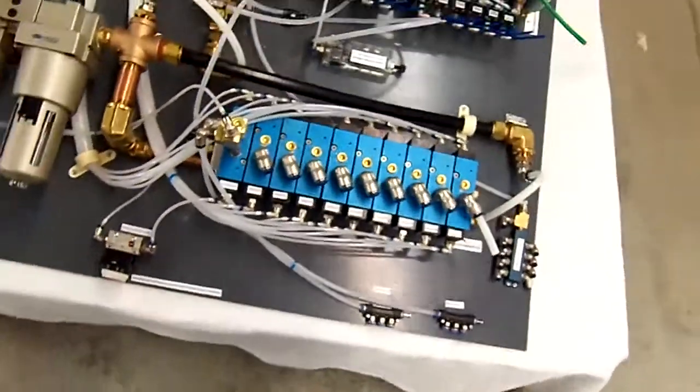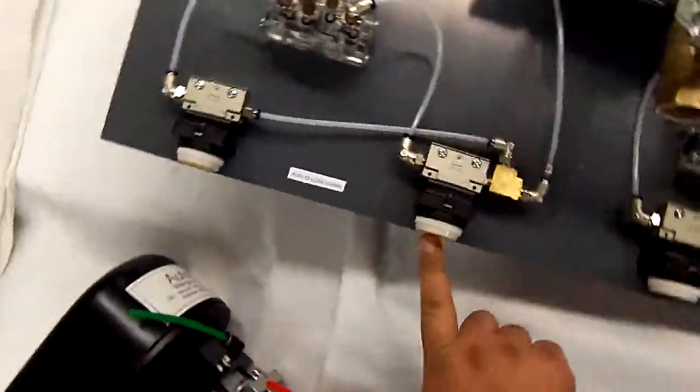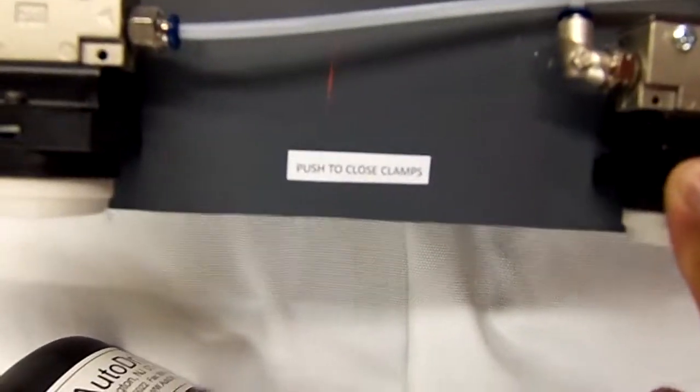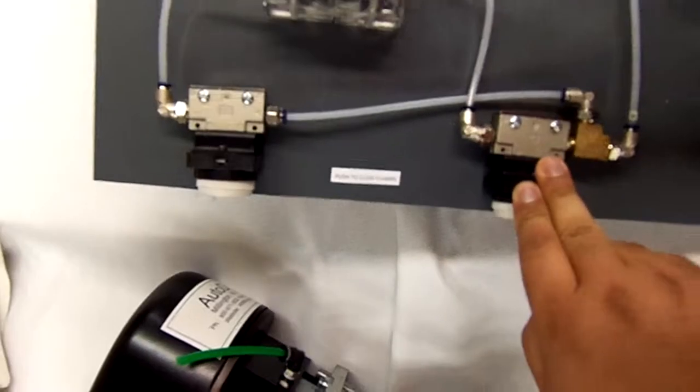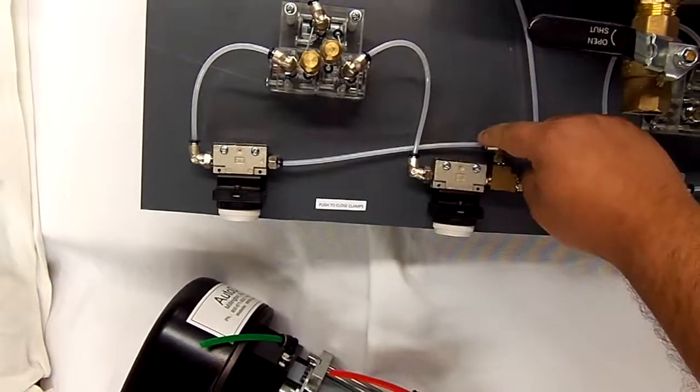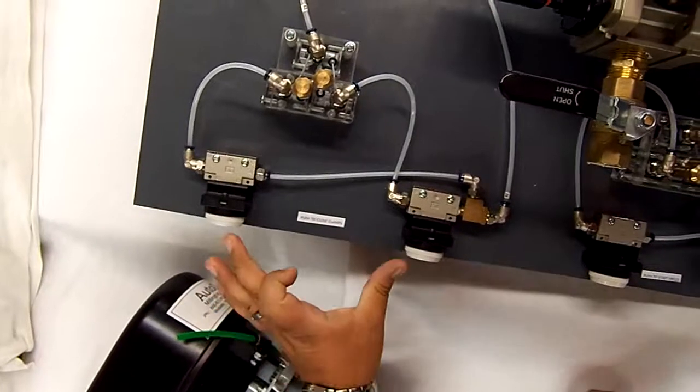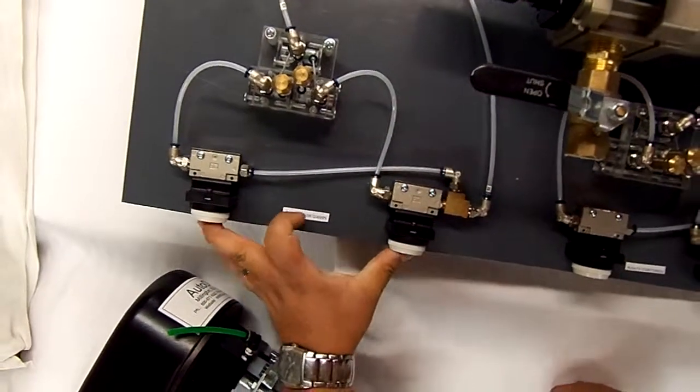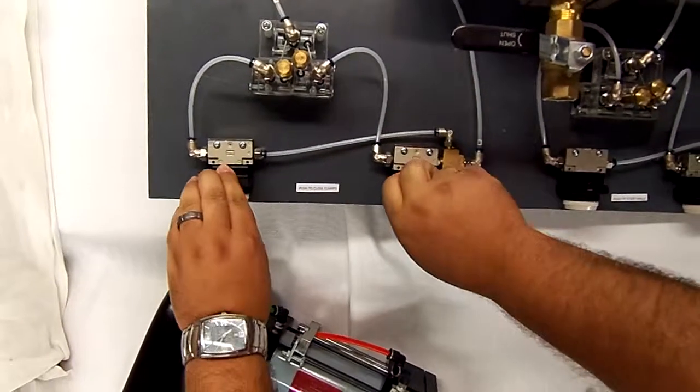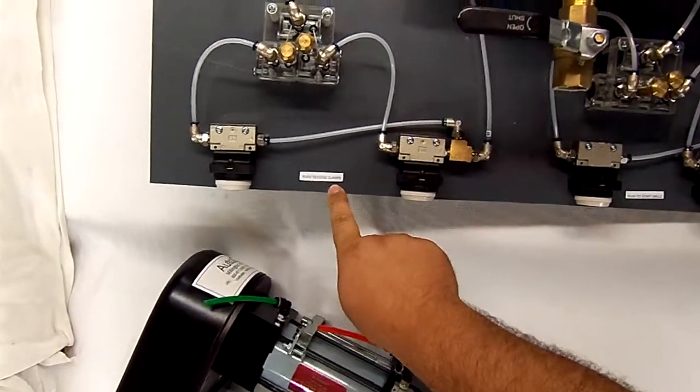Once the clamps are in the open position, the operator will hit these two buttons simultaneously. These buttons need to be removed from this mounting table and moved to a more strategic location. I would definitely recommend that this tube be lengthened so the buttons are farther apart so the operator could not use one hand to hit both buttons at the same time.